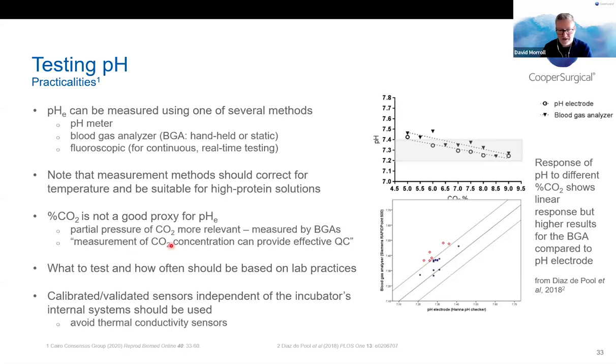But if that's the only system you've got, then it's better than nothing. But ideally what we're going to do is use a pH system and test directly. Now, what to test and how often should be based on lab practices, but typically it will be when we introduce a new batch of medium or we're testing new media. That's the minimum requirement.